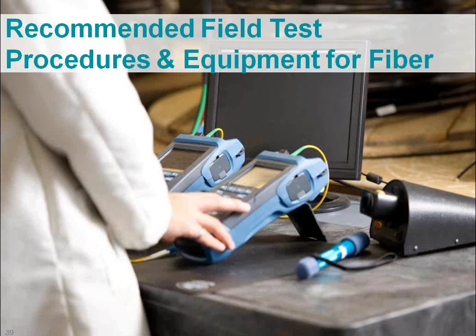We've seen many issues arise from people testing in the field. Many people do not know how to handle or properly use the testing equipment. Manufacturers of equipment will usually provide training on their own test equipment, but sometimes they're not very helpful. We do recommend people bring in their test gear to us. We'll inspect it, verify it's working properly, and teach them how to operate it and understand the results that they're getting from the equipment.